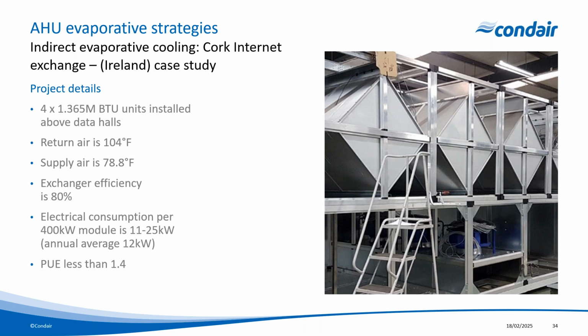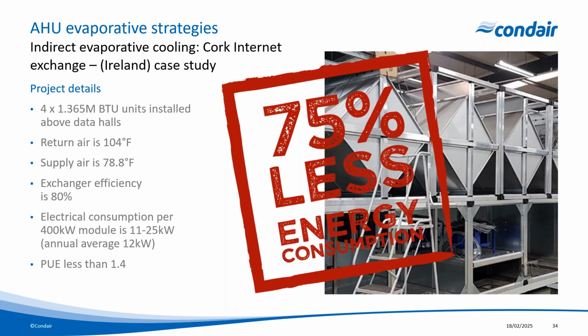So this gave an overall power utilization efficiency, or PUE, of less than about 1.4. So compare this to the previous legacy design, which resulted in about 75% less energy required by going to an indirect evaporative cooling system on this new design.